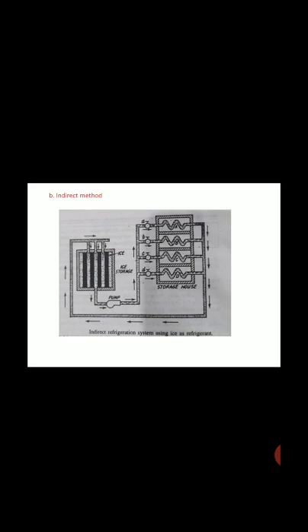In the indirect method of ice refrigeration, ice is isolated from the storage space and cooling of articles is carried out by the circulation of brine. The ice is supplied to the compartment where it surrounds vertical tubes containing brine. Cold brine is recirculated through the storage space A, B, C, D to cool the articles, and finally the brine returns to the ice compartment. This cycle repeats again and again. This system is more suitable for larger plants with no danger of food infection. The major disadvantages are that the area required is too large and the cost is more.